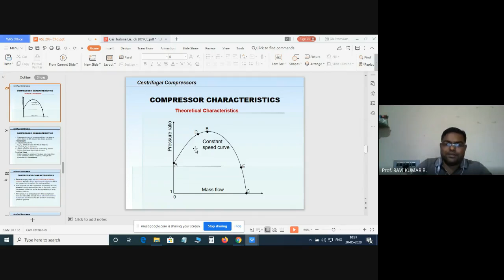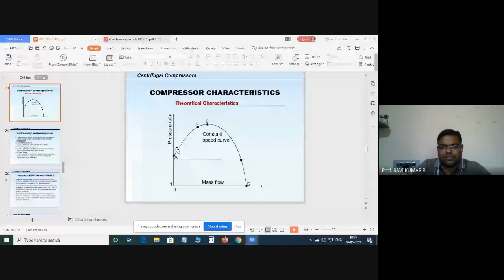A point will be reached when the downstream pressure drops sufficiently with respect to the inlet flow condition. Then again the compressor will pick up, pressure rise will take place, and then again surging will happen. So it will be a pulsation phenomenon, right? Continuously it will pick up, then again it will surge. So instability will happen in the curve. That's why we pointed out earlier that this section of the curve will not be like this kind of curve. There will be a lot of fluctuations because of the surging phenomenon.